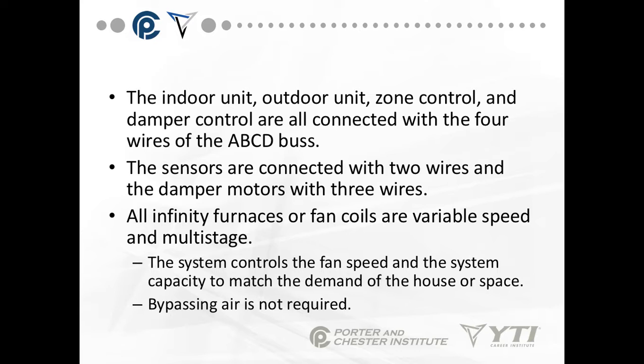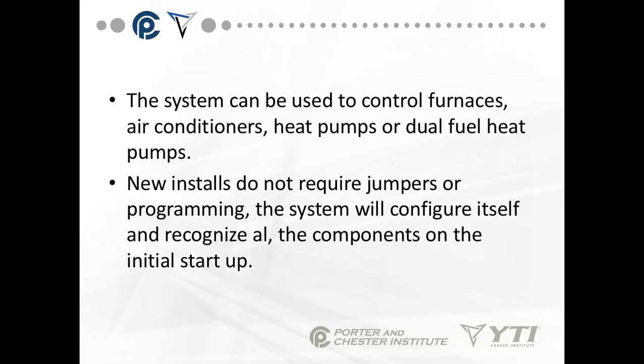All Infinity furnaces or fan coils are variable speed and multi-stage. The system controls the fan speed and system capacity to match the demand of the house or space. Bypassing air is not required because the fan speed will decrease with fewer zones calling. The system can control furnaces, air conditioners, heat pumps, or dual-fuel heat pumps. New installations do not require jumpers or programming because the system will configure itself and recognize all components on the initial startup.